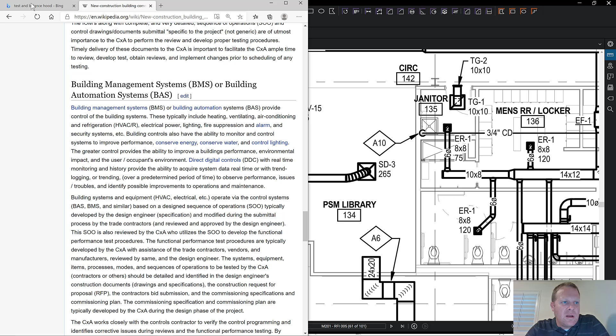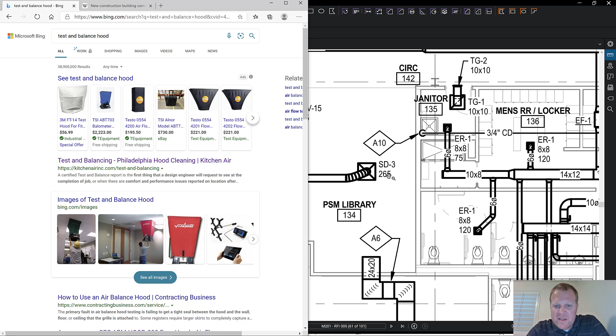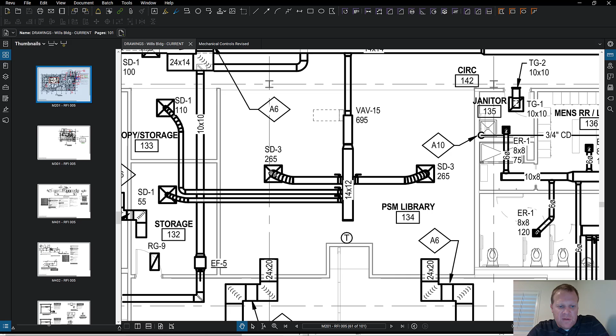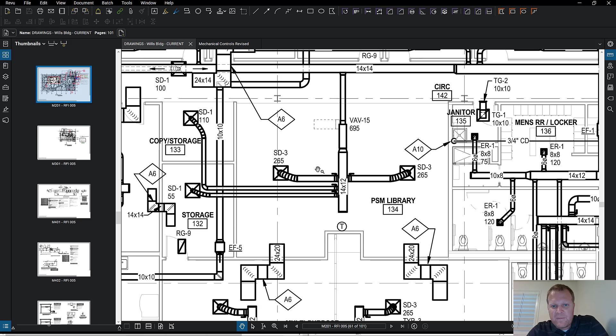And what do they put over the top of it? A hood, with somebody standing in the space over the diffuser, reading how much air is coming out, then opening up the ceiling, turning this a little bit, and rereading it to say, okay, that's correct, we got the right amount of air here. Then come over to this one, read it, we need to adjust a little bit, so come over to the damper and adjust. That's the general idea behind test and balance.